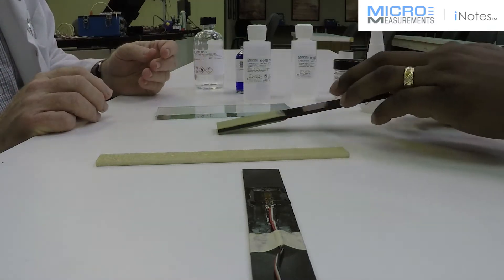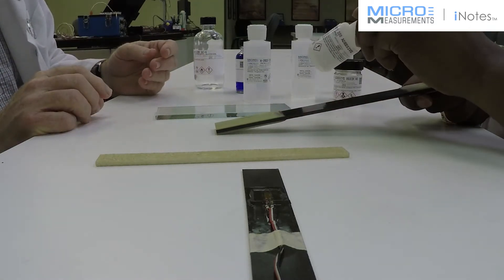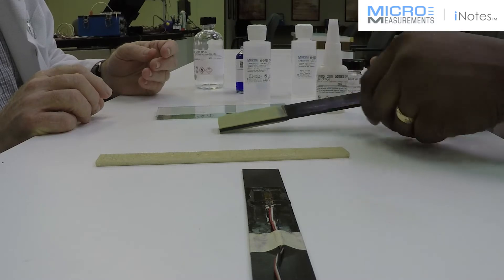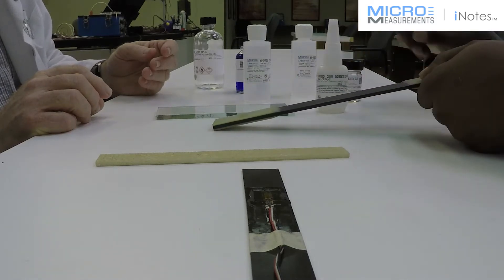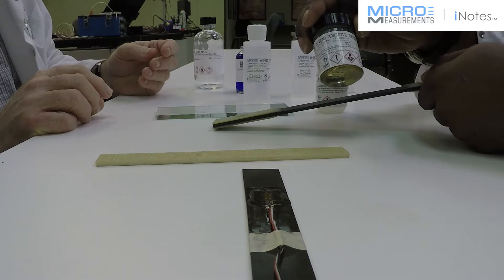Well, for the smooth surface here, I would use our M-Bond 200 adhesive. However, for the coarse or more rough surface that we see here, I'd go with our AE-10.